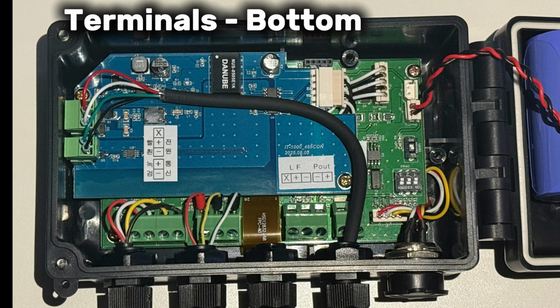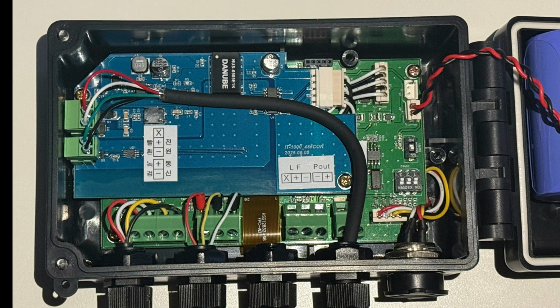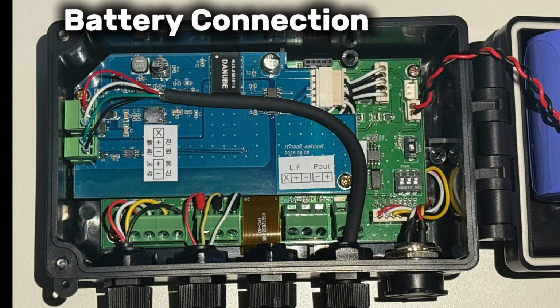On the far left, these are terminals for the pressure and temperature sensors. In the center, you will find the meter pulse input to receive signals from the gas meter. On the right, these are terminals for RS485 communication and alarm out to send status signals to external devices. The 3.6 volt lithium battery connector is located on the side of the board. To replace the battery, simply disconnect this and plug in the new one.